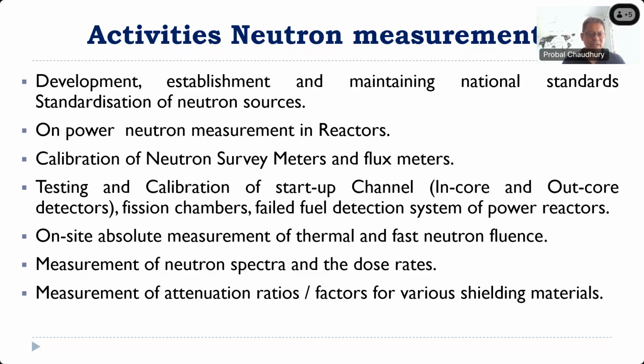Then of course we have testing and calibration of startup channel. So when the reactor starts, we have to have different levels of monitoring, like fission chambers, and then also we have some new failed fuel detection system, which is based on neutron measurement in the nuclear power plants. Then on-site absolute measurement of thermal and fast neutrons. Thermal neutrons have lesser energies, whereas fast neutrons have higher energy.